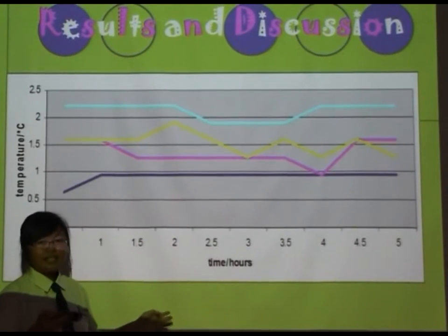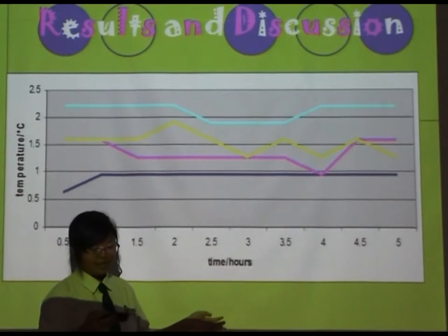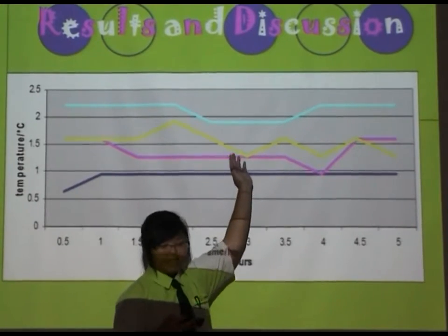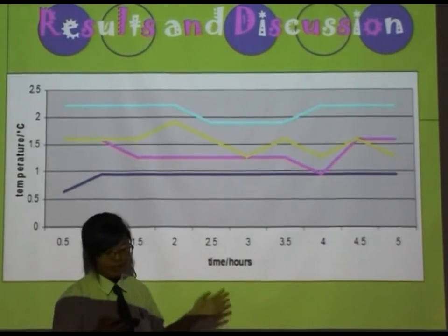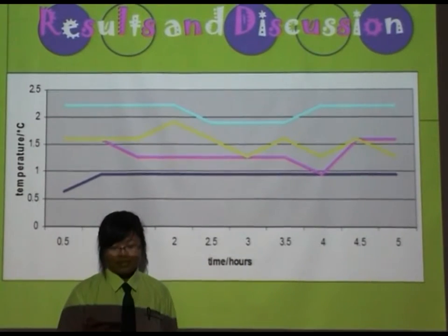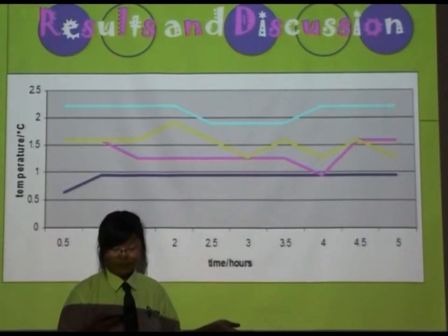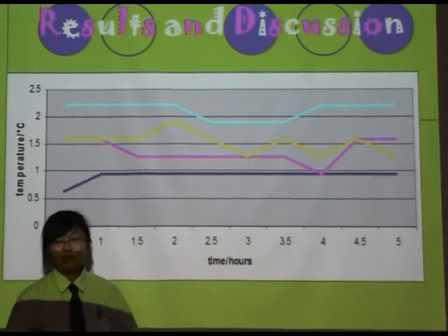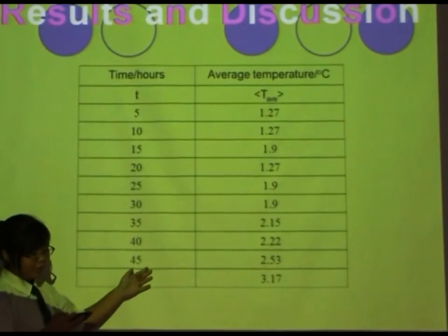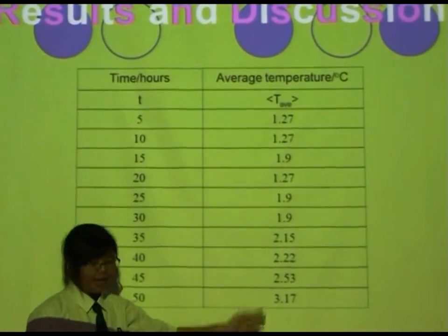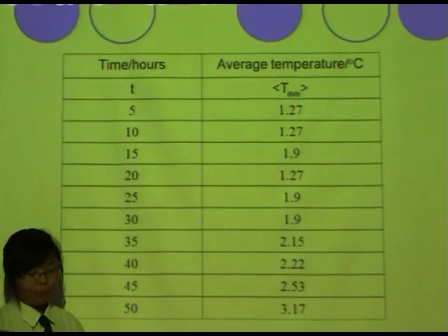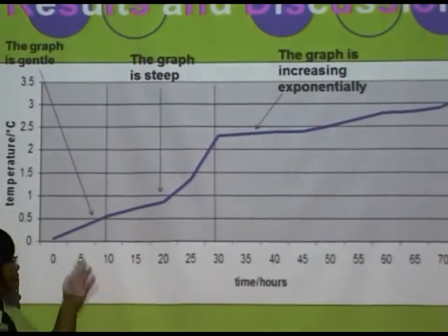So as the days progress, the aircon filter becomes dirtier, which shows that the temperature difference between the aircon and the outside room increases. This shows that there is a correlation between the temperature difference and the air filter. After we had this table, we can add each point and find the average temperature of each day, and this is how we correlate to the 1 point in the next graph.